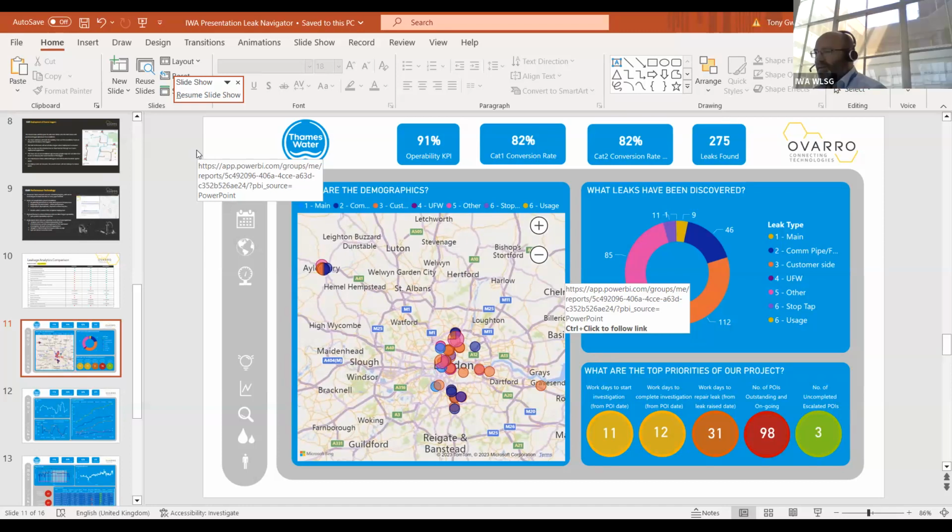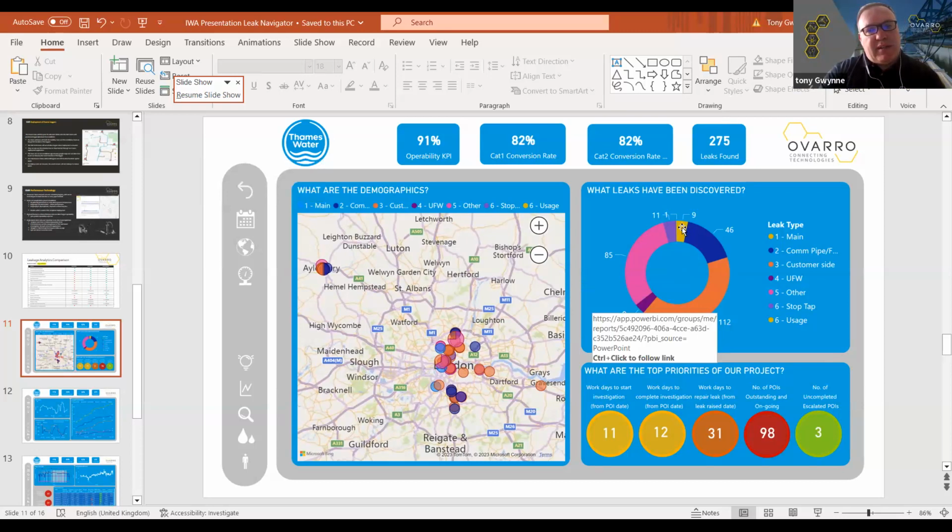If that's helpful. Well, we know from the fact that small diameter plastic pipes attenuate leak noises very quickly. Yes, absolutely. I mean the mix of leaks we're finding, and I think in Thames it's quite interesting, because if you look at United Utilities, the Thames percentage is lower on mains, for instance. We are picking up a lot of the smaller leaks initially on the data. There is probably a lot more smaller leaks. There could be private leaks. In United Utilities, in the DMAs we're working in, we're probably around 35% burst main against the criteria. So we feel that UU are probably in a better place with the leaks that they've found to date in the DMAs we're in. We're only in plastic DMAs in United Utilities, and we are picking up some high percentages of burst mains rather than smaller leaks.